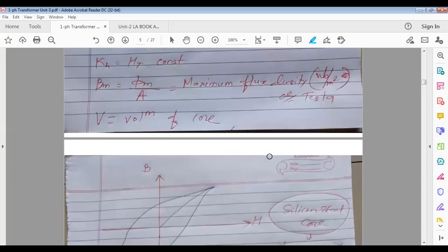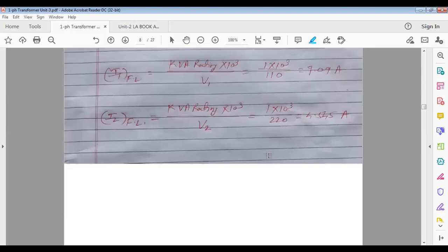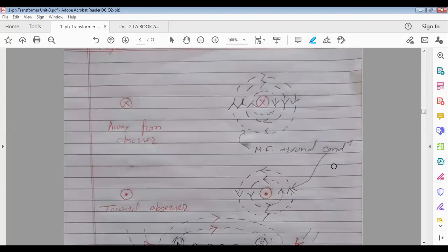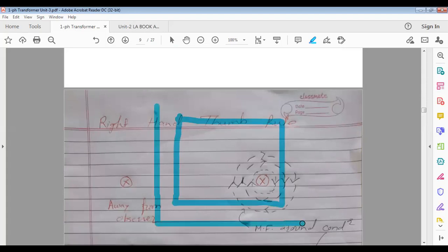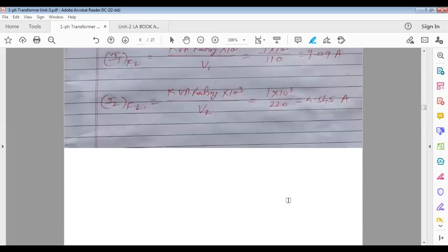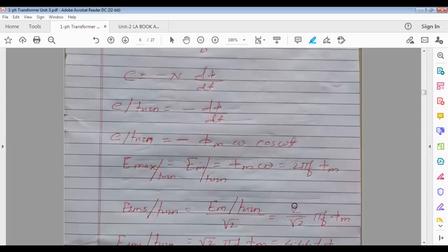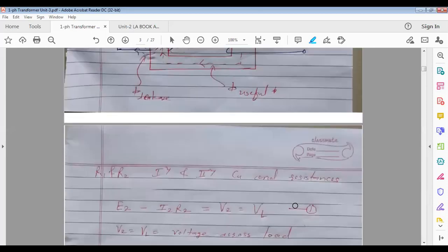Now the thickness of this insulating material depends on how much voltage you are going to apply across primary and how much voltage across secondary. Now the rectangular shaped, centered magnetic core of the transformer is either square or rectangular, and it is not solid, it is laminated construction. Laminated construction means what? Why is it made up of silicon steel? Because silicon steel's relative permeability is very high.